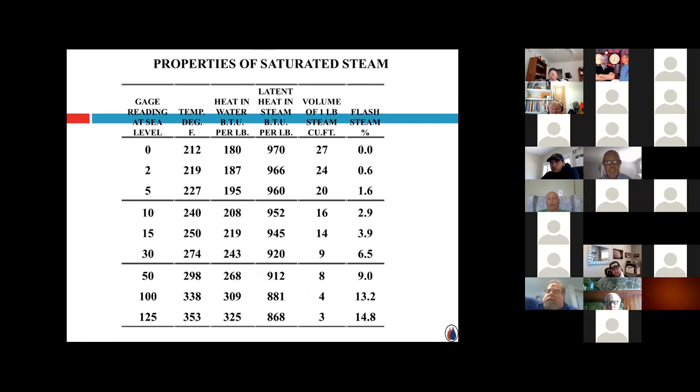Pressure is there for overcoming frictional resistance of steam flowing through pipes — and that was taken care of by the installing contractor 75 to 100 years ago. He would size pipe based on a one-ounce pressure drop per 100 feet of pipe; on a two-pipe system, maybe two ounces per 100 feet. Just like friction resistance in a hydronic system, the gas encounters the same thing rubbing against pipe walls. They sized pipe larger to keep pressure drop low and run boilers at very low pressure by design.